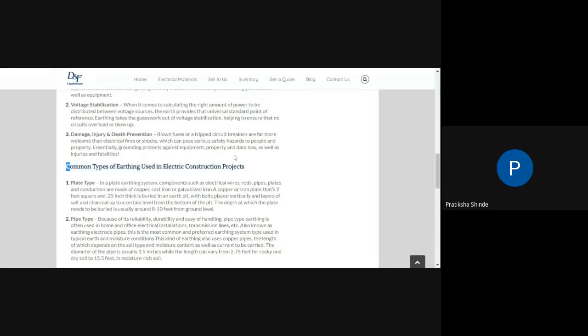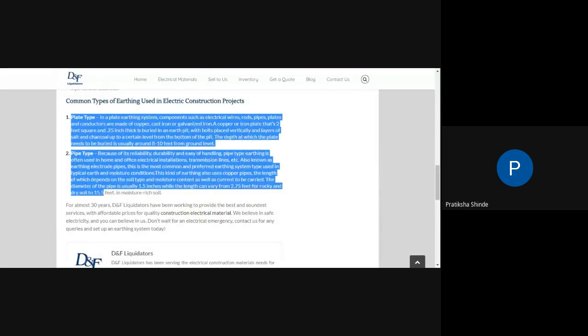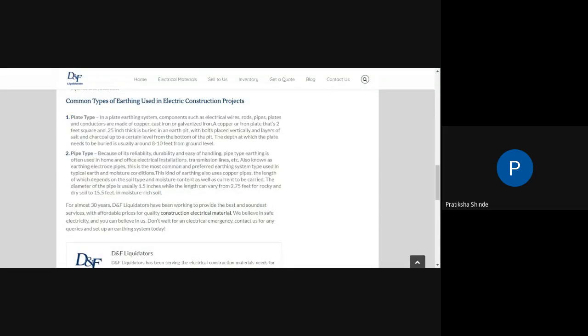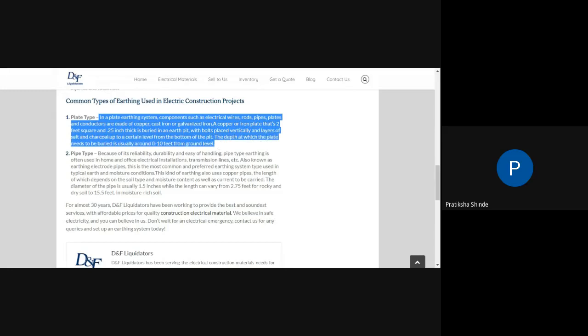Now, common types of earthing. The first one is plate earthing, and the second one is pipe earthing. What is the difference between plate earthing and pipe earthing? In plate earthing, the components used are electrical wire, rod, pipe, plate, and conductor made of copper, cast iron or galvanized iron. A copper or iron plate is put inside the earth pit, with a bolt, placed vertically, and a layer of salt and charcoal up to a certain level from the bottom of the pit. Generally one plate of copper or one plate of iron can be used for plate earthing.